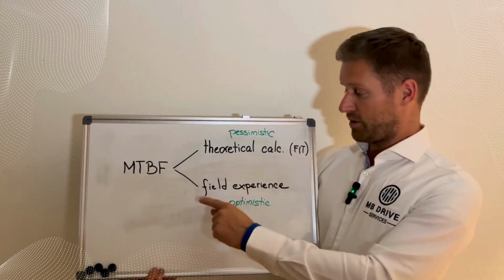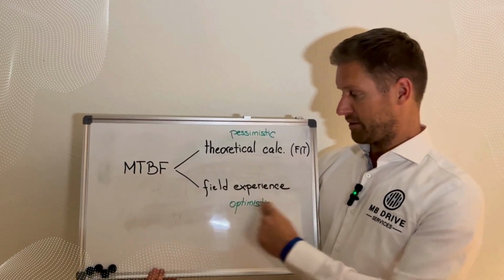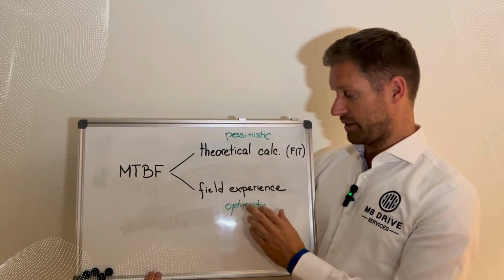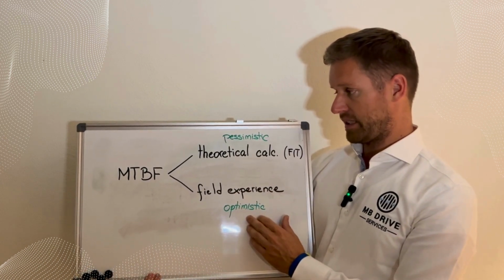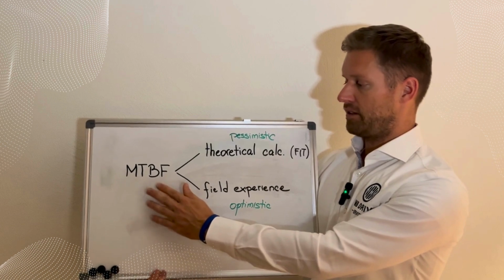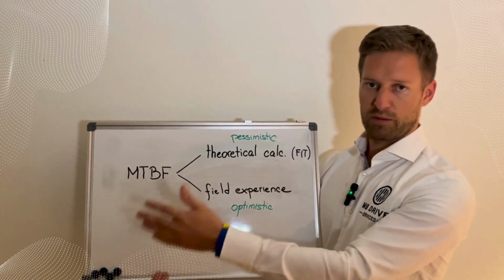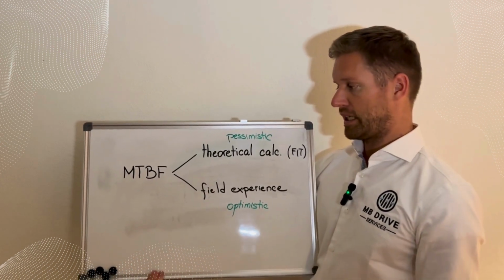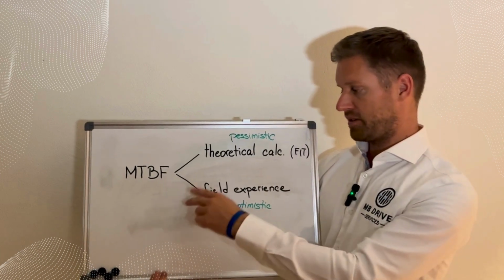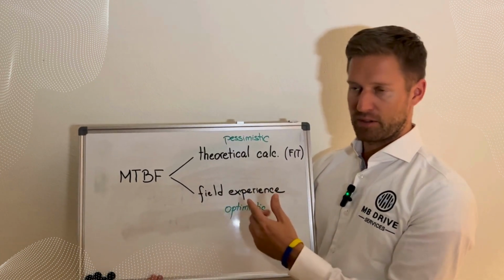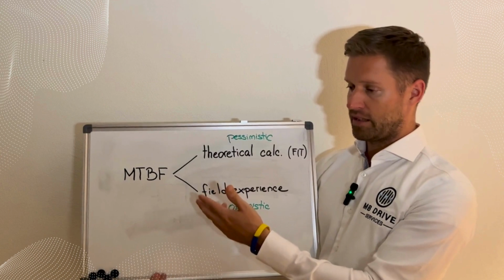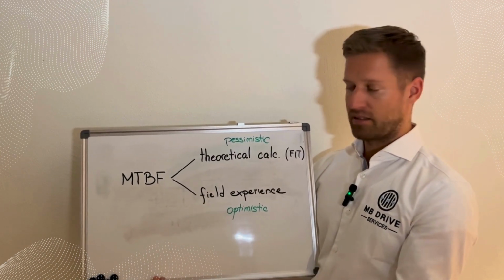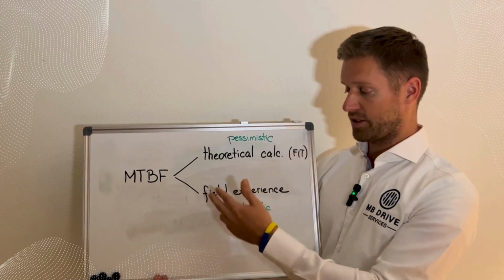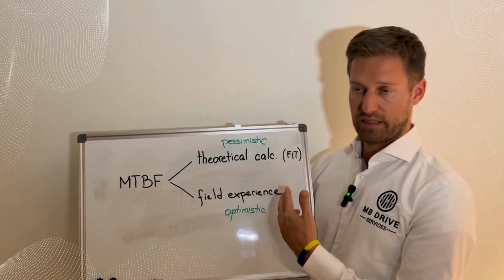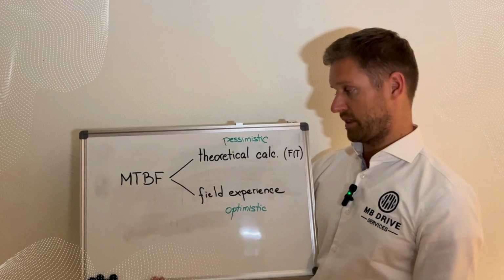So what I want to say, this field experience typically results in more optimistic figures. So if you have a figure of MTBF for a transformer or VFD or motor, and it's not stated what the base for the determination of the value is, then I recommend you ask back, is it a theoretical calculation or is it based on field experience? Because it makes quite a big difference.